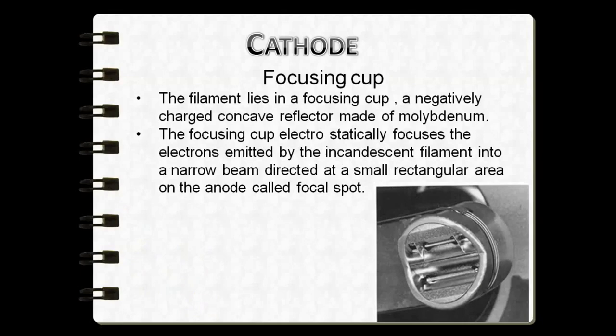Next, we have the focusing cup. The material of choice is molybdenum. It is a negatively charged concave reflector cup of molybdenum that houses the filament. The focusing cup electrostatically focuses the electrons emitted by the incandescent filament into a narrow beam directed towards a rectangular area in the anode called the focal spot, facilitating the movement of the electron cloud towards the target.